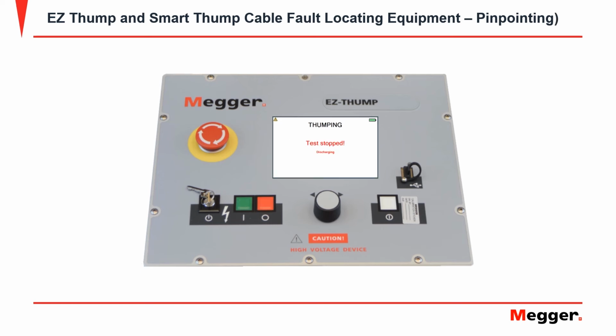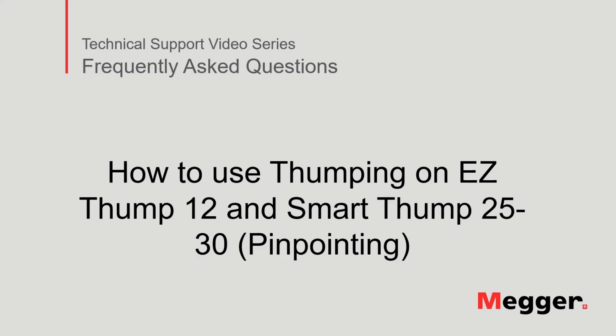Once manually stopped by either the rotary knob, the red HV off button, or the E-stop, it will show test stopped and then it will begin to discharge the cable. Once the unit and the cable is discharged, it will show test stopped and by what method the test was stopped. This concludes how to use thumping on the Easy Thump and the Smart Thump.